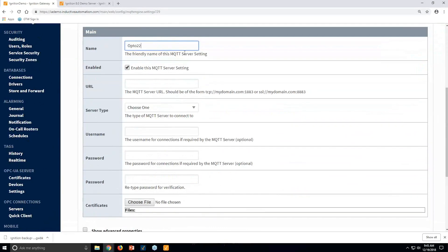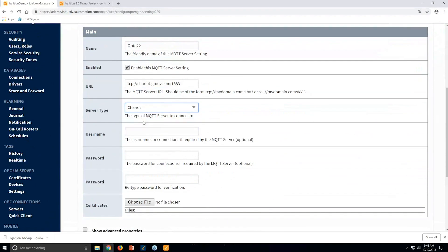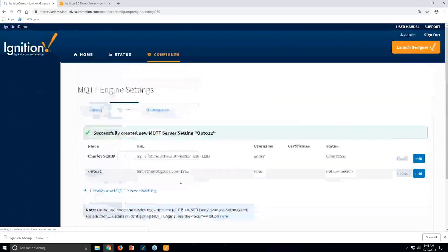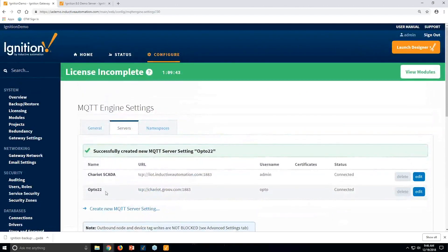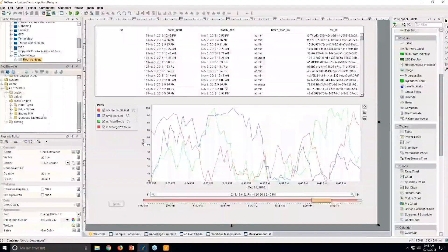Opto 22 has a broker that's out there, and we can connect to it. This is TCP, chariot.groov.com, port 1883. I pick the type — it's a Chariot type — give it a username and password, verify that password, and this ends up making a connection out. When I switch over to my designer and look inside, I have access to all the tags that are out here.